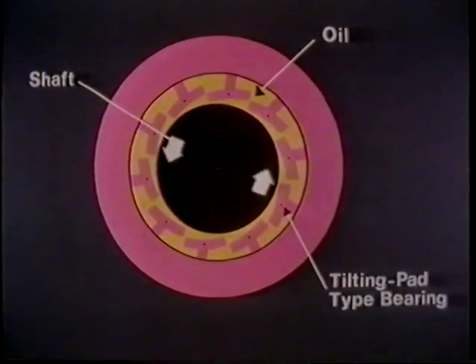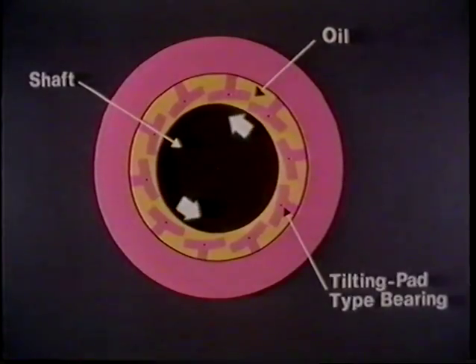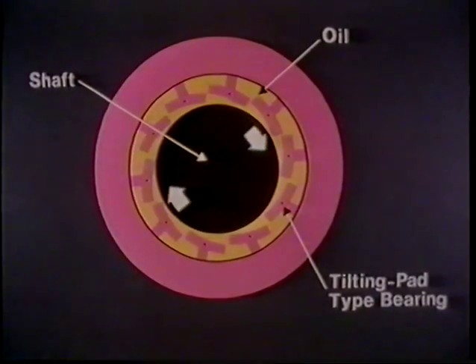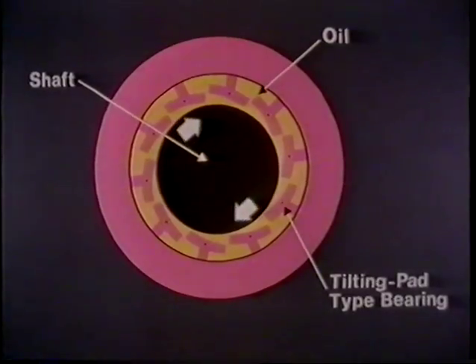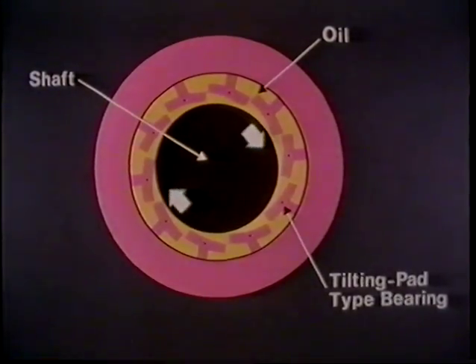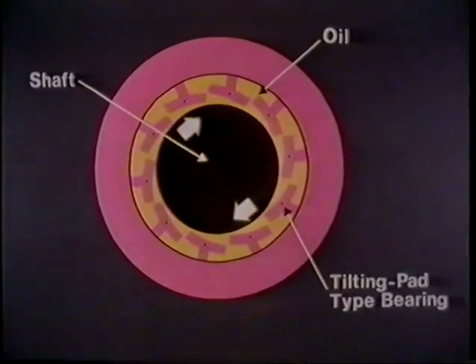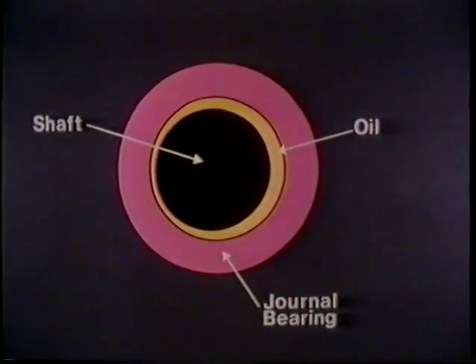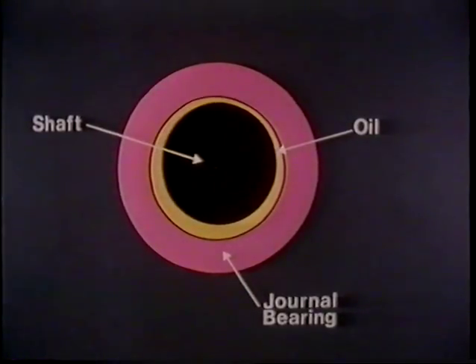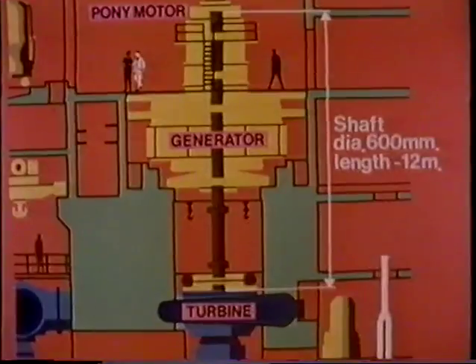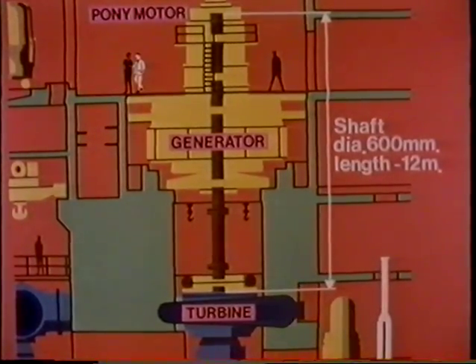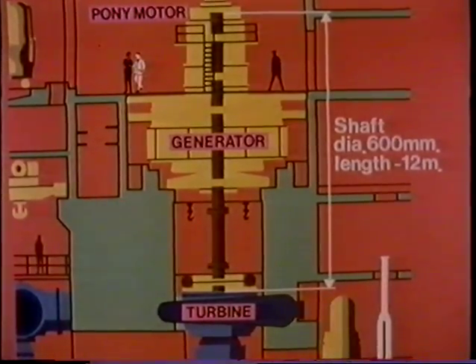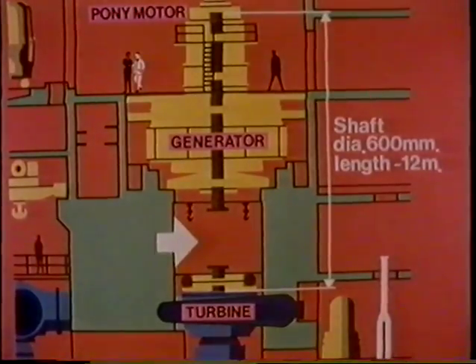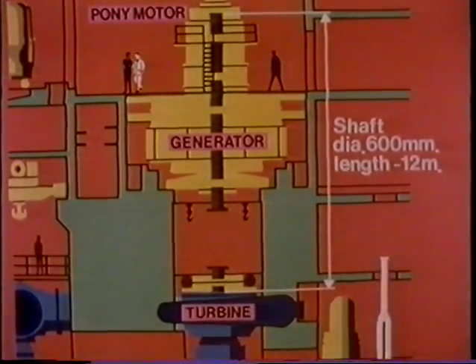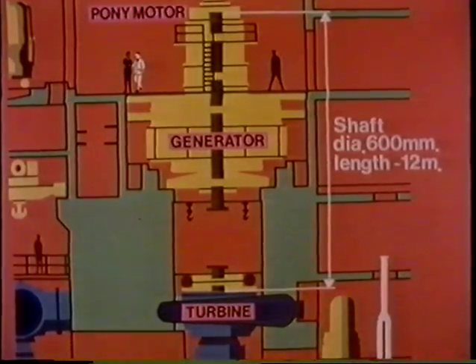The turbine bearing is a center-pivoted pad type. This provides a closer control over the shaft movement compared with a plain journal over the same temperature rise, hence reducing wear on the carbon seals and increasing the stability of the shaft. The machine torque is transmitted by shafts of manganese-bearing high-carbon steel. Since vertical units do present problems of accessibility, an intermediate shaft can be removed so that the head cover and runner of the turbine can be raised without disturbing the generator.